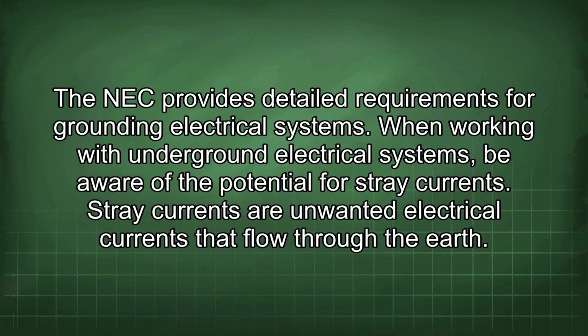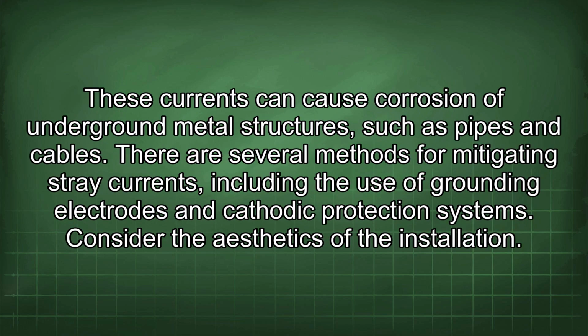When working with underground electrical systems, be aware of the potential for stray currents. Stray currents are unwanted electrical currents that flow through the earth. These currents can cause corrosion of underground metal structures, such as pipes and cables. There are several methods for mitigating stray currents, including the use of grounding electrodes and cathodic protection systems.